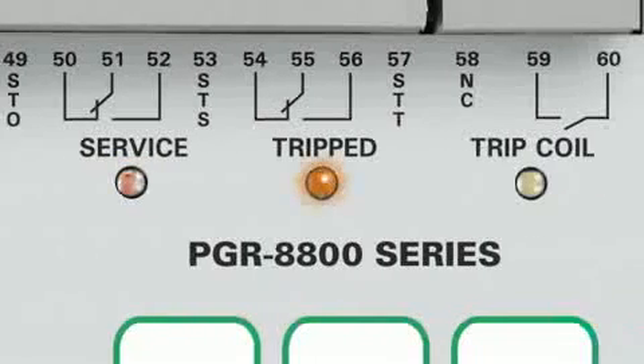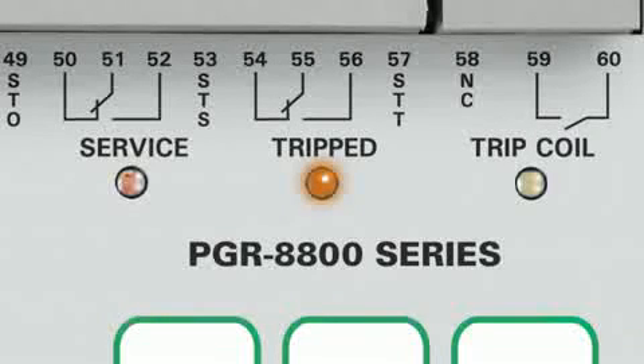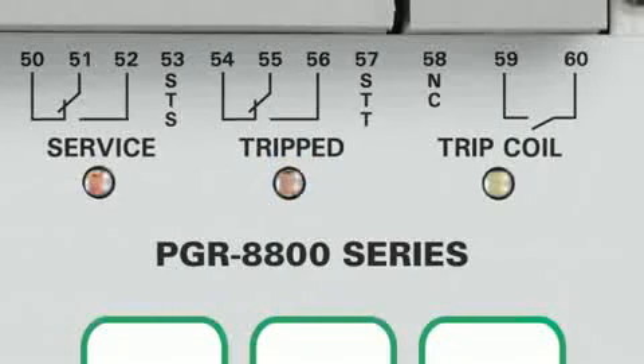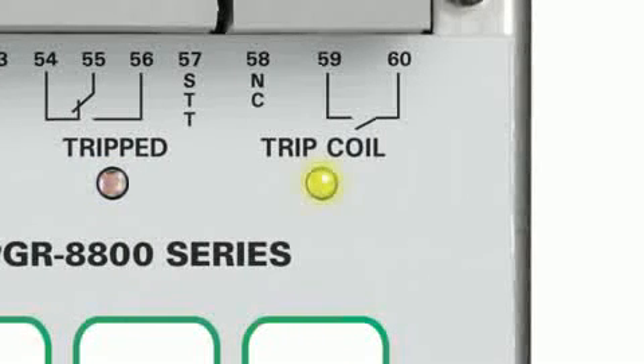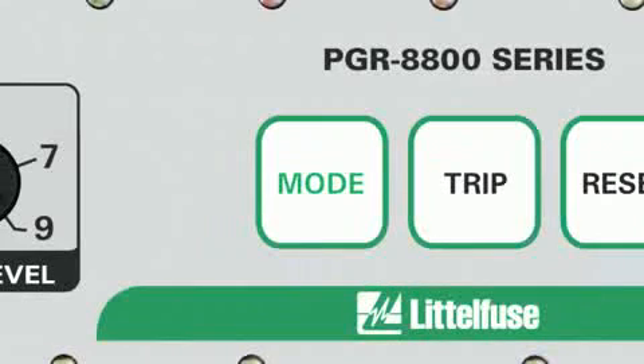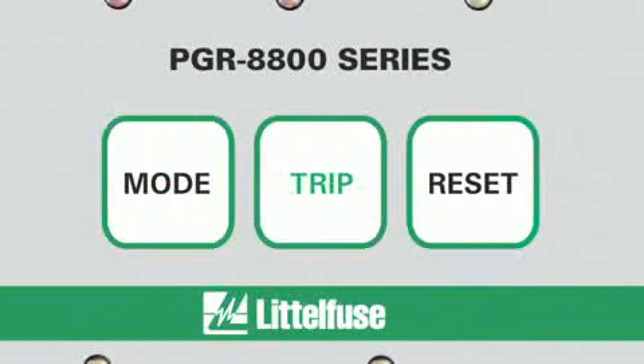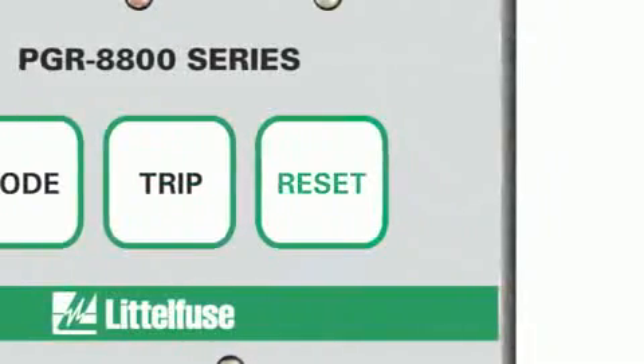Trip can be used to send to a system to let you know that you had a trip, or it can be tied to a secondary breaker. This is our trip coil. It's an IGBT that's tied to the shunt trip of the breaker. The IGBT transistor acts as a fast-acting switch to engage the shunt more rapidly than if we were to use a dry contact. Our mode button toggles the unit into service mode for an initial setup. The trip button you could also use to test the unit. And we have the reset to reset after a fault.